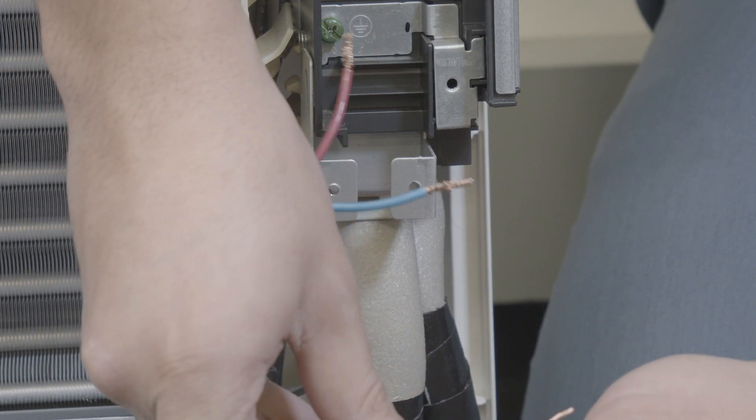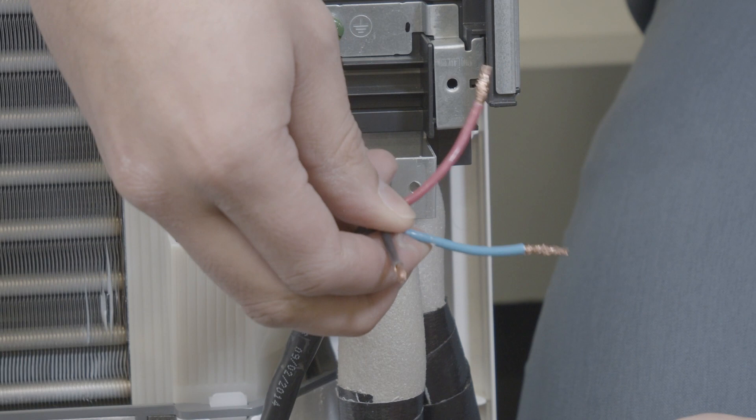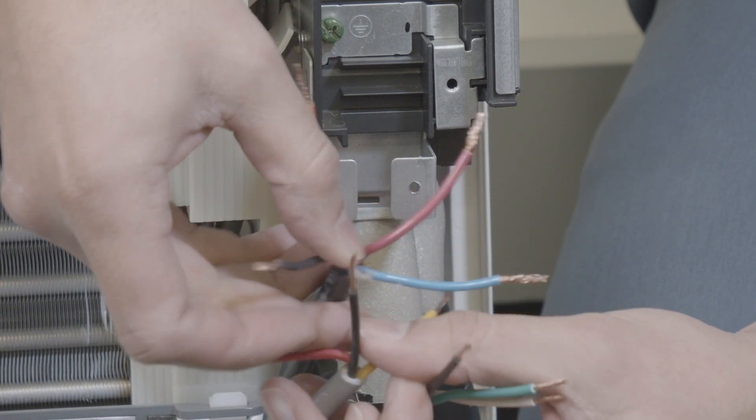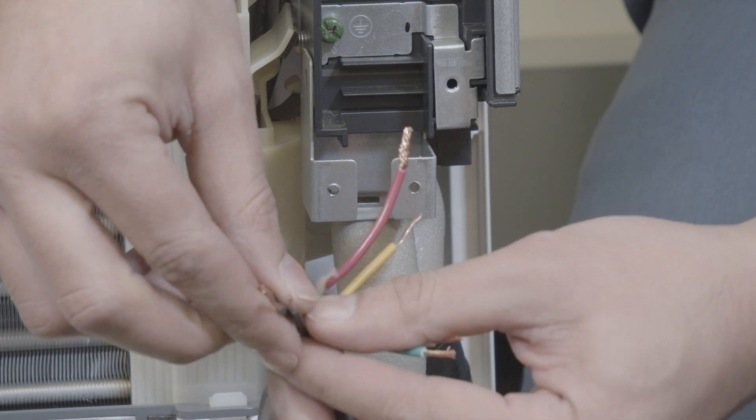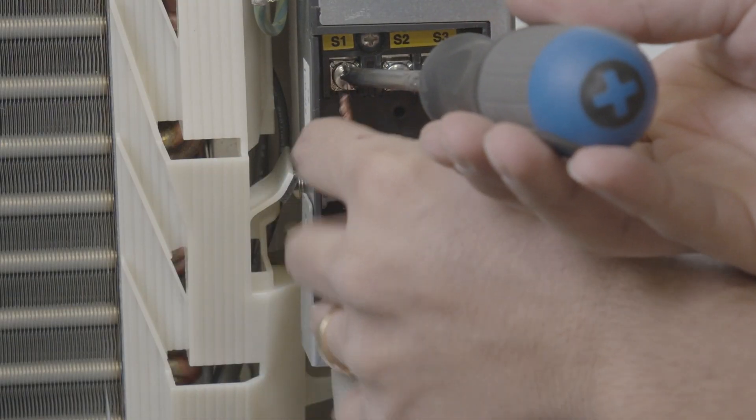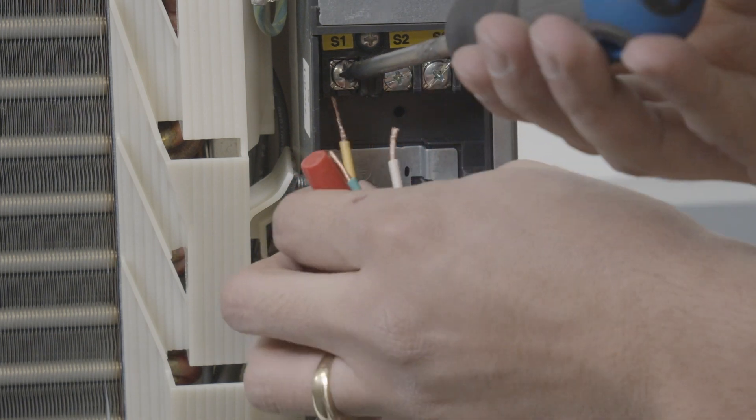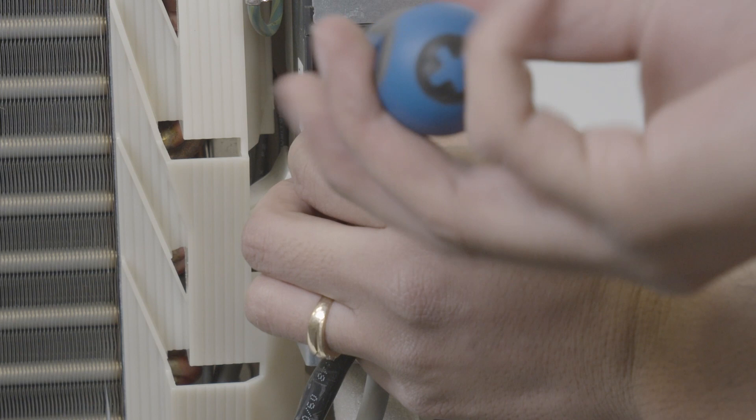In order for the pump to get voltage during alarm, you will have to wire nut the S1 wire coming from the outdoor unit, along with the black common wire from the pump's alarm circuit, and the black line voltage wire powering up the pump. Next, terminate the yellow, normally closed alarm wire from the pump to the S1 terminal of the indoor unit.